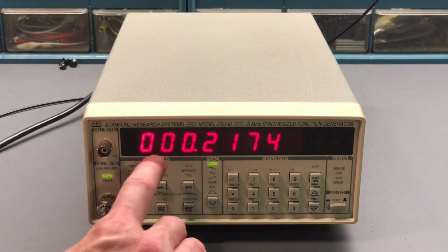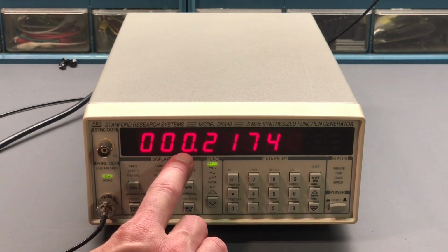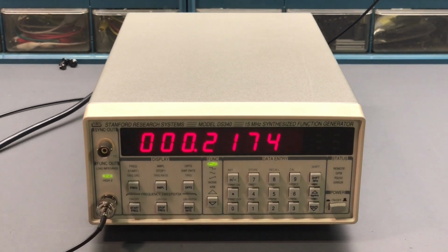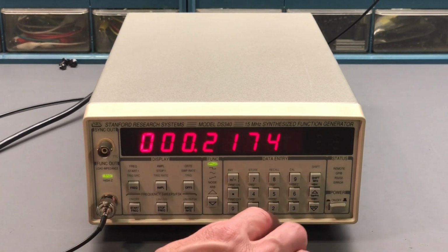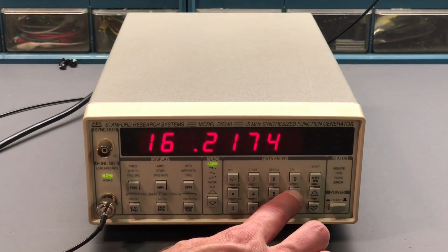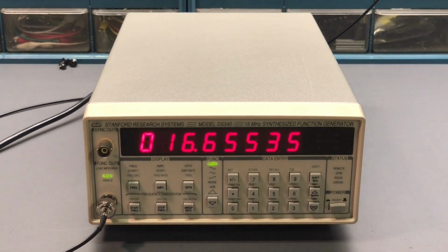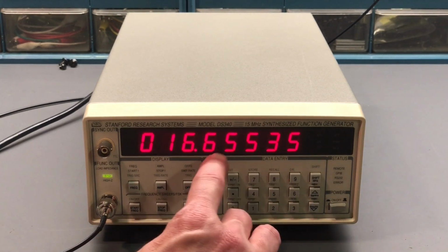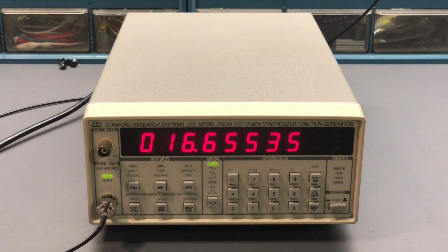So with the cal bytes over here, with this value flashing, if you need to change this, and there are a total of 642 total cal bytes, so quite a few in the whole system, affecting many different aspects of the instrument, attenuator settings, output amplitude, and so on. If you need to change this value, let's say you want to go to cal byte 16, you could hit 16 like so, press that. So that would be displaying cal byte 16. You can see the value over here is the actual cal byte value, so 65,535. And that's actually what that should always be set to. That's the pre-attenuator's reference value.